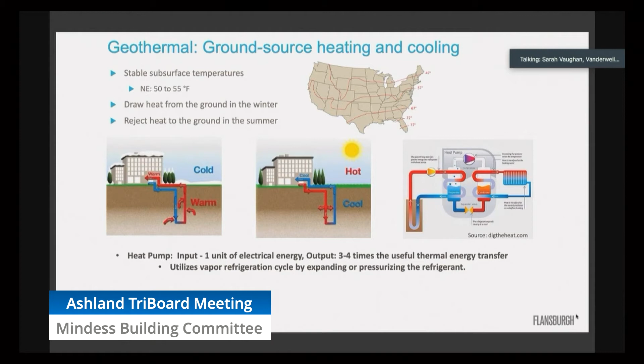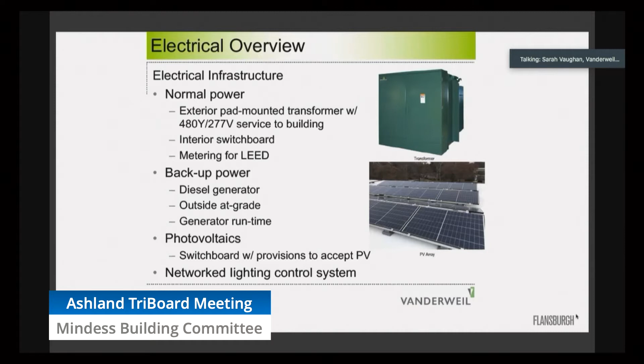For the electrical system, we'll have a new service from the utility and an exterior pad mounted transformer with new 480 volt service to the building. We'll have an interior switchboard, and we're specifying metering and sub-metering to meet LEED requirements. For backup power, we have a diesel generator located outside on grade, and the building will be designed with provisions to either accept PV or get PV on day one. So our building will either be net zero ready or net zero on day one, depending on whether the PV is installed, but the infrastructure will be there. We'll also have a networked lighting control system.